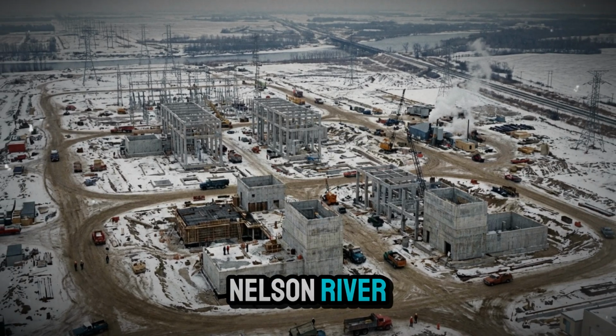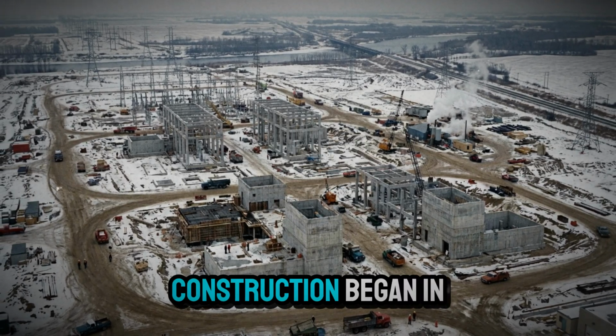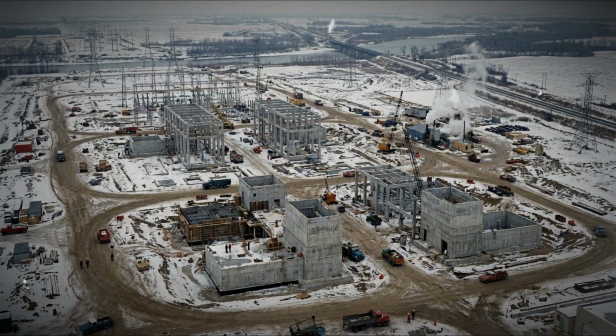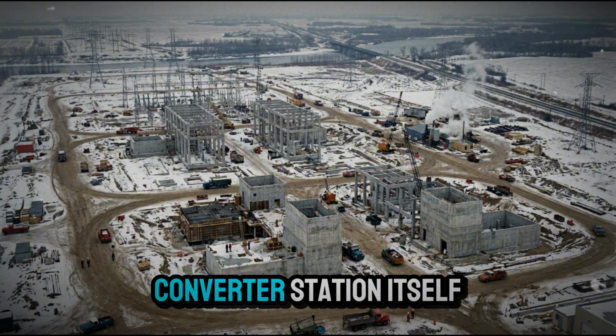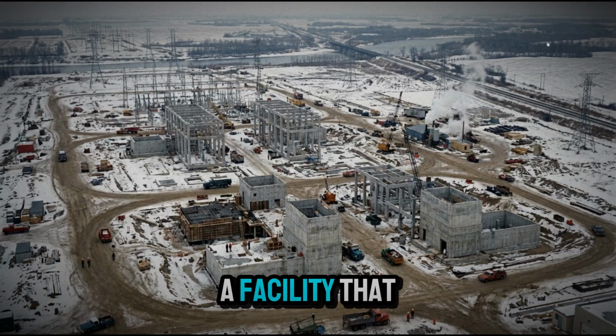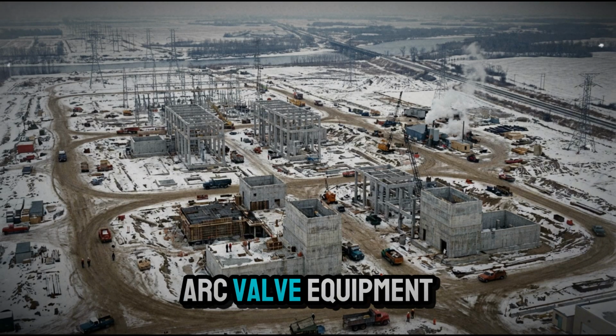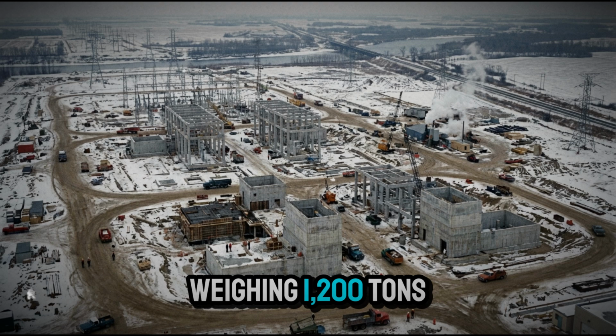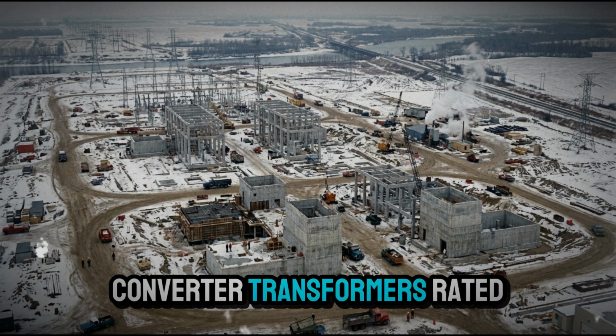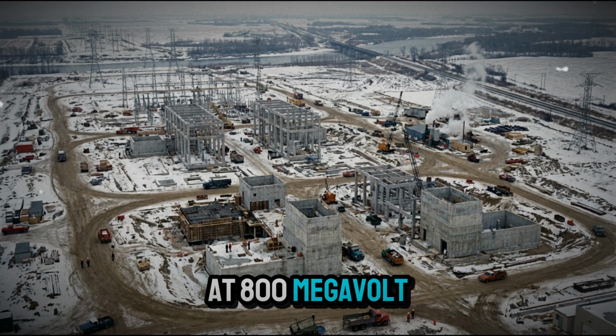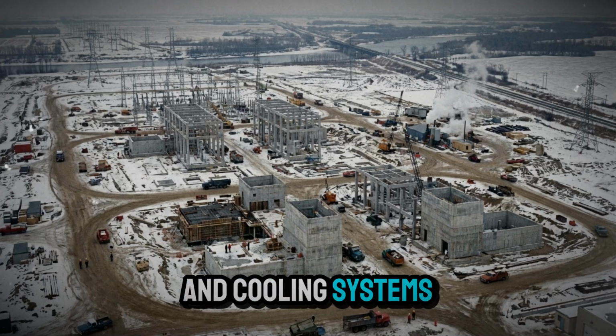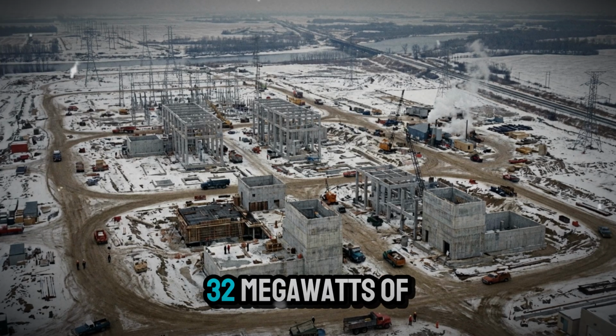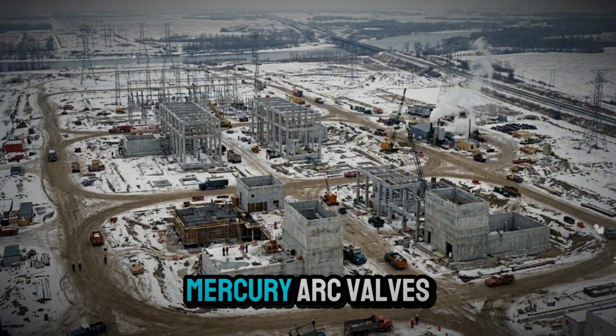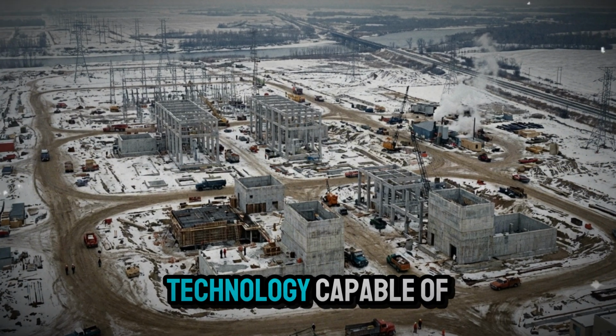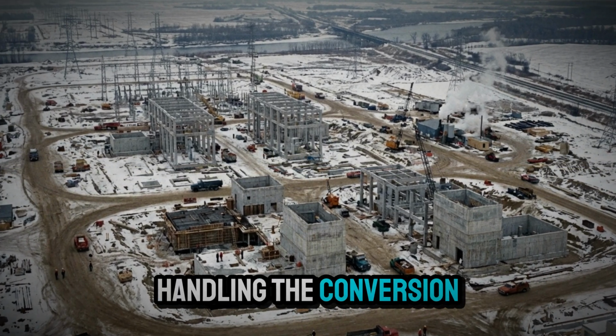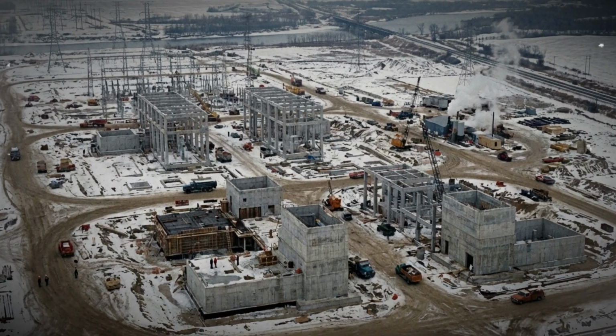Back to the Nelson River. Construction began in 1970. The first challenge was the Dorsey Converter Station itself, a facility that would house mercury arc valve equipment weighing 1,200 tons, converter transformers rated at 800 megavolt amperes, and cooling systems capable of dissipating 32 megawatts of waste heat. Mercury arc valves were the only technology capable of handling the conversion at the required power levels.